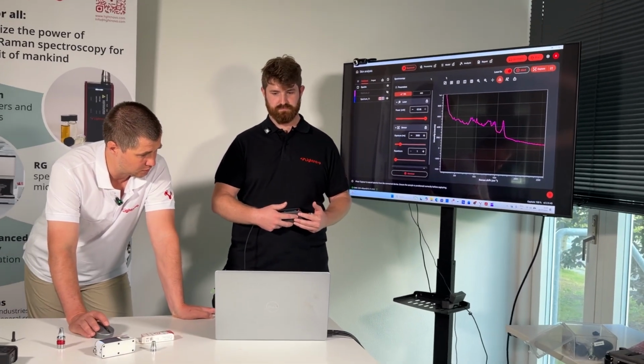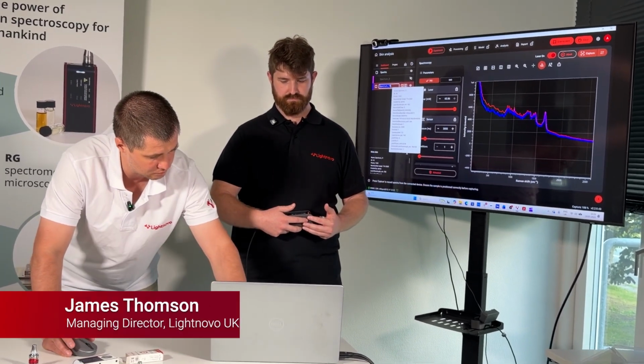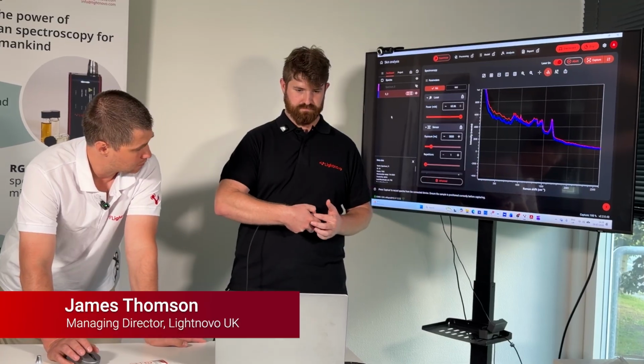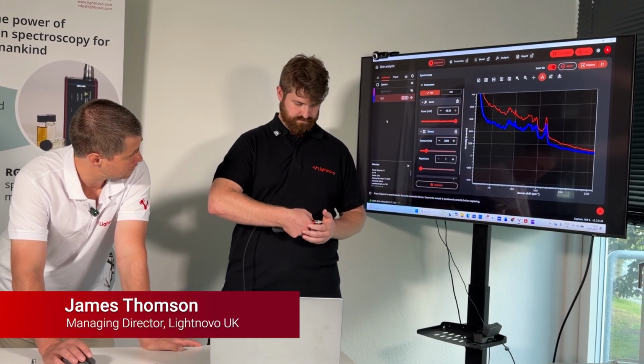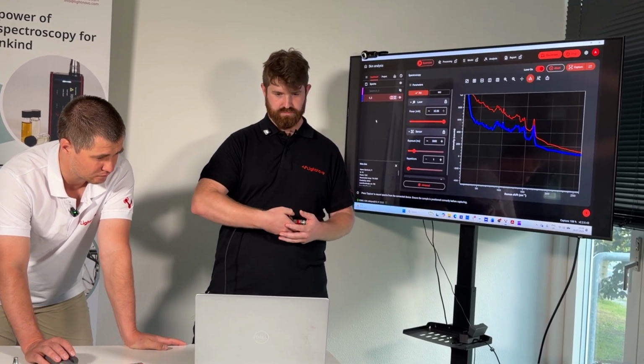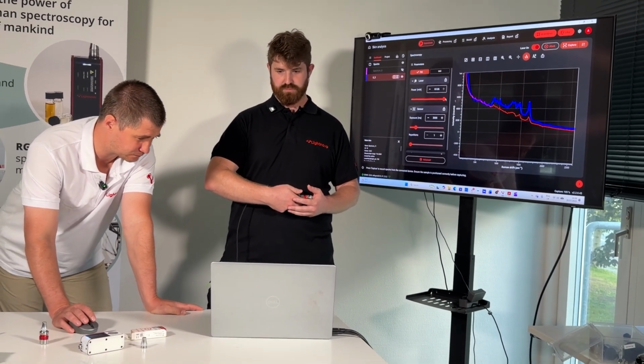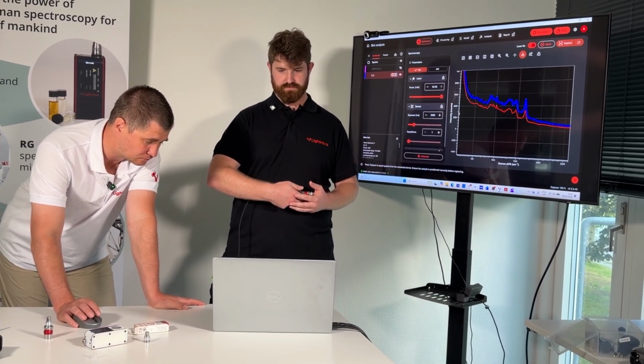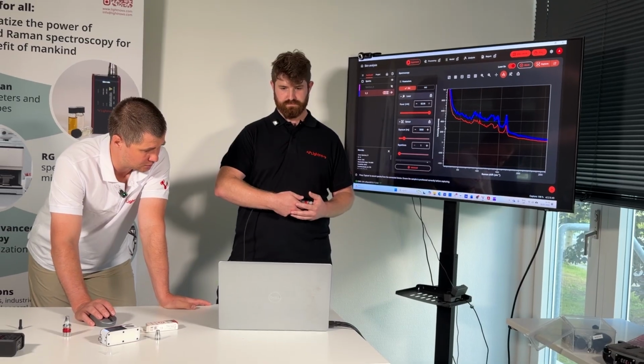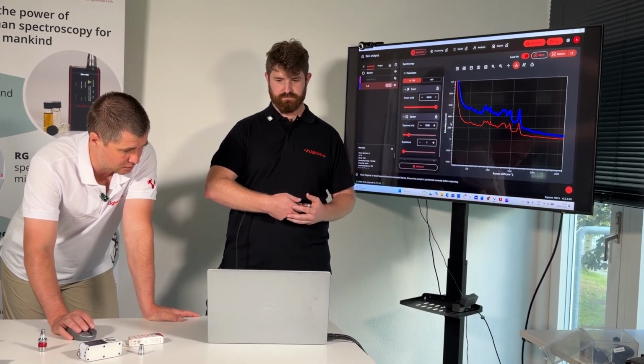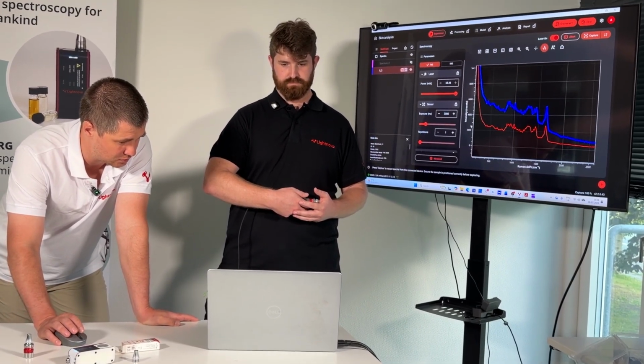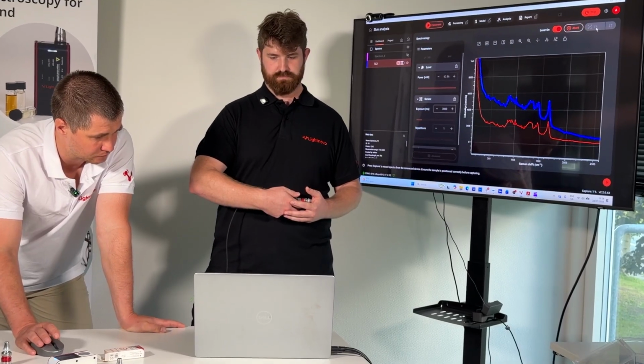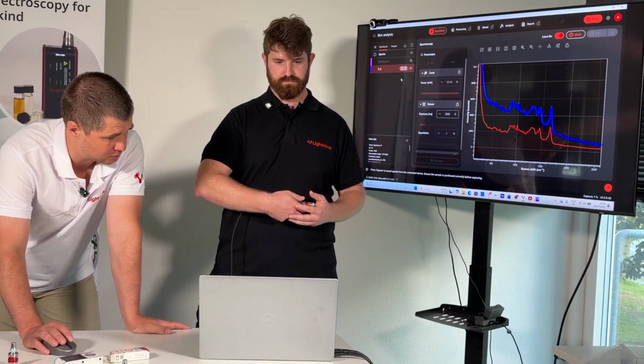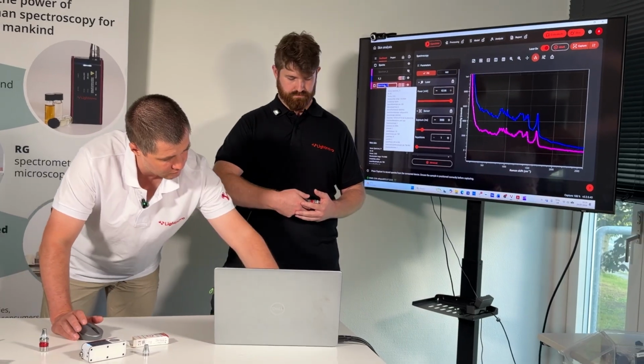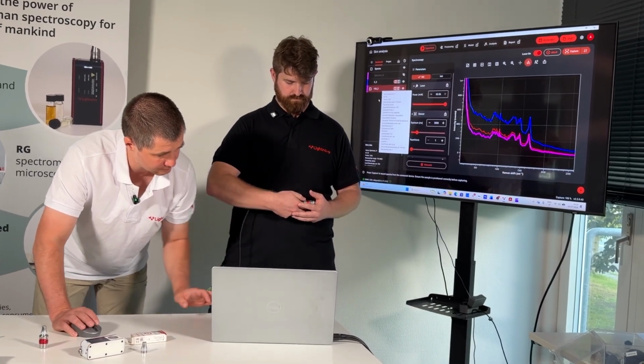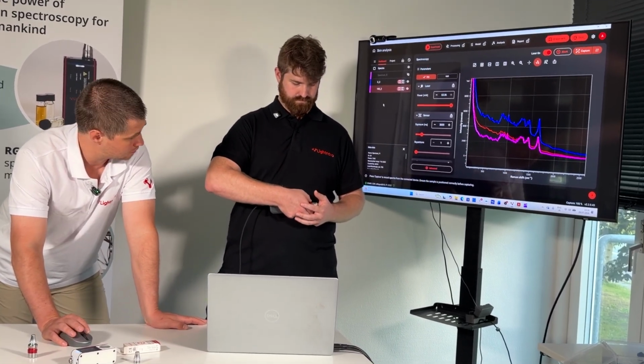And this is what we call the spectrum at 0 micron penetration depth. Okay, then please move to 100 maybe. Yeah, so I have moved to 100. We see the signal is less intense, and I would press capture again. And after it's acquired, I will call it here 100 micron. Okay, 200. Yeah.